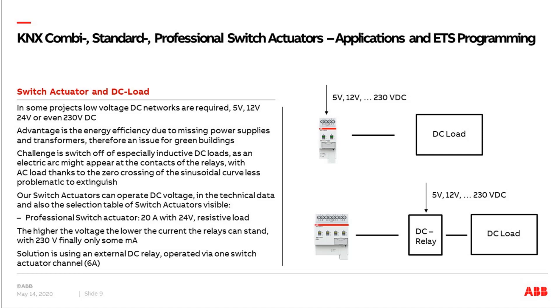Of course, what is always possible is to say it's too risky and use an additional DC-capable relay made for DC switching, with the load behind it. Then our switch actuator only controls the control circuit of the relay, with no load current through it. In principle it's possible to switch DC directly, but be careful and please check whether it's possible for your specific case.